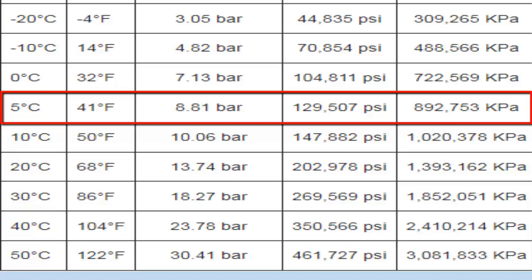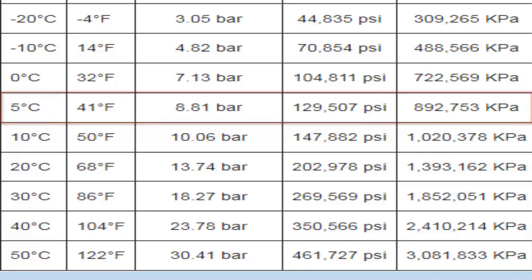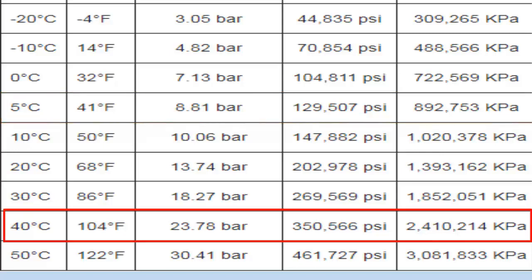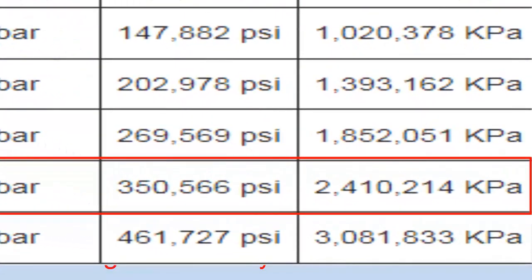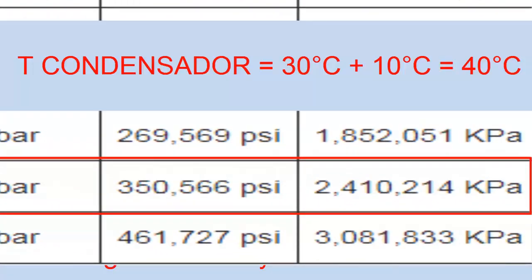In the case of an air conditioning unit, the high pressure, with the equipment running at a condenser temperature close to 30 degrees Celsius, we are going to have a high pressure of a little over 350 PSI A.